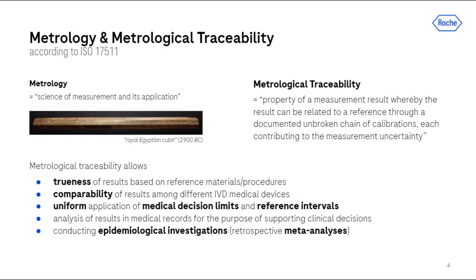ISO 17511 is all about metrology, the science of measurement, and metrological traceability — the unbroken traceability chain from a result back to its reference. The first metrological standard was established by the ancient Egyptians back in 2900 BC, who defined a certain length with the so-called royal Egyptian cubit, which helped them to highly precisely build their monuments like the pyramids. Metrological traceability allows and guarantees trueness and comparability of results, uniform decision limits and reference intervals, and method-independent epidemiological investigations and meta-analysis.